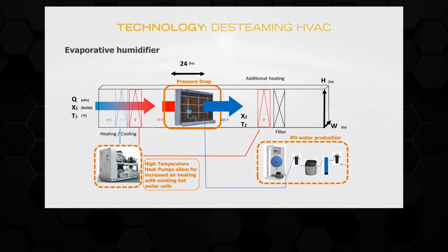Another interesting project that we did at Skywalker was replacing hot water and steam used for heating, ventilation, air conditioning. The Skywalker plant has close to 25 AHUs that maintain humidity between 45 to 65% at various zones depending on the product manufactured. Through a heat pump network, we delivered chilled water and hot water for heating and cooling loops of the AHUs. But we have discussed how that happens already. So we'll skip that part and move to the interesting part of this project, which was introducing adiabatic cooling into AHUs that resulted in complete elimination of steam for humidification.